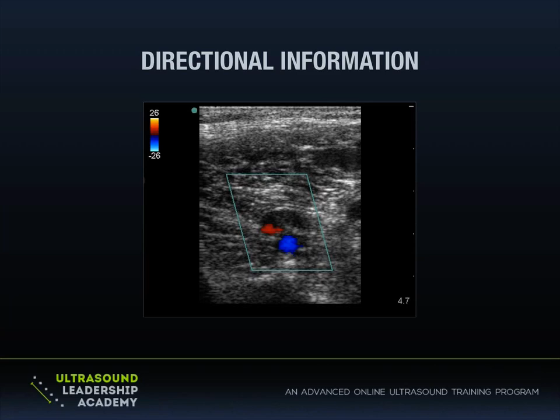Now, you can also look at color with non-directional information, and this is just asking the question, is there a Doppler shift? Not which direction the Doppler shift is happening, but is there a shift at all? And in this case, the display tells you that you're not going to get directional information off of it. It's going to give you one color only, which is going to tell you whether or not there's flow. Now, the higher flow is going to be a brighter, lighter yellow, as opposed to the darker flow down here, which is going to be more of a dark maroon. And you can see that even in these vessels here, where the center of the vessel that you're imaging has that nice bright yellow and the outside has the darker maroon because it's lower velocity.